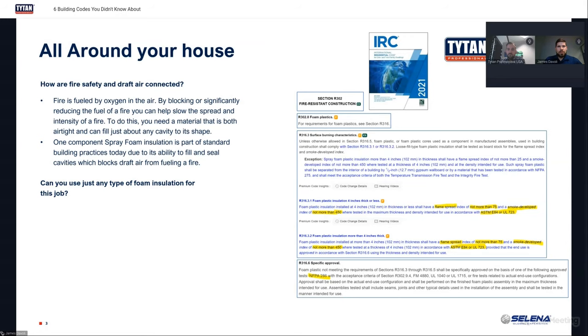And there are really a few other things that have come about. It's not necessarily always there per region, it can vary, so always check your local building codes. But per region, they've started to become more accustomed to having an orange dye for ease of inspection. They'll definitely check to make sure the product is either ASTM E84 or UL 723 tested and listed. If there's that special approval needed via the NFPA 286, it's going to need to have that on the product information. And lastly, for multifamilies, the bigger residential type builds, they're going to need that ICC-ES report.